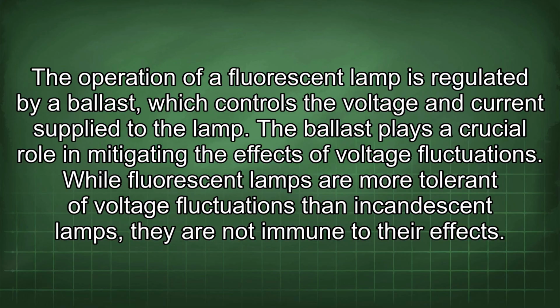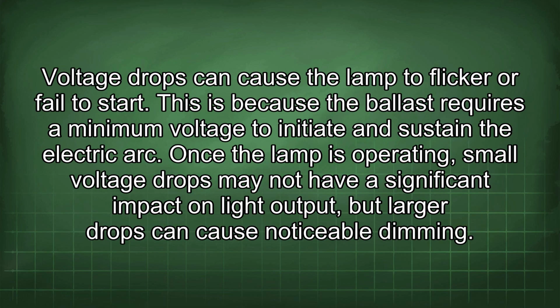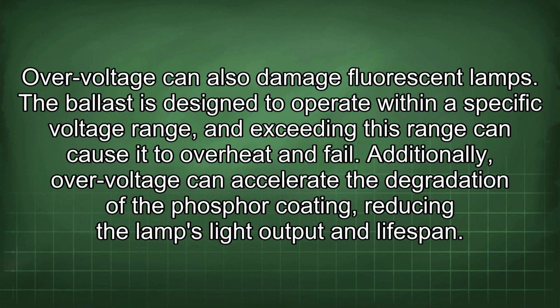While fluorescent lamps are more tolerant of voltage fluctuations than incandescent lamps, they are not immune to their effects. Voltage drops can cause the lamp to flicker or fail to start. This is because the ballast requires a minimum voltage to initiate and sustain the electric arc. Once the lamp is operating, small voltage drops may not have a significant impact on light output, but larger drops can cause noticeable dimming. Overvoltage can also damage fluorescent lamps.